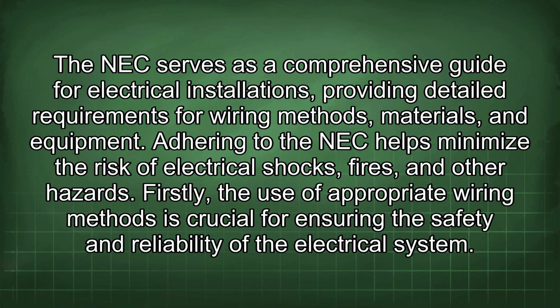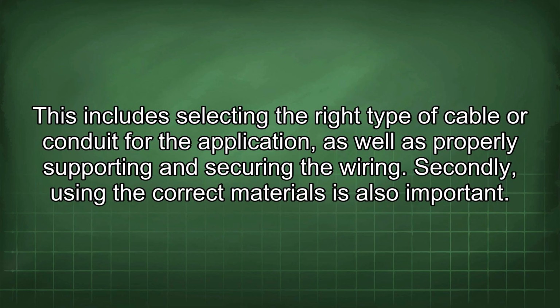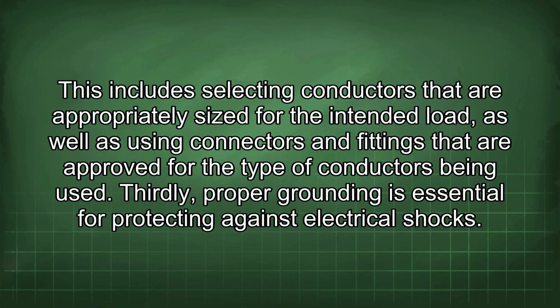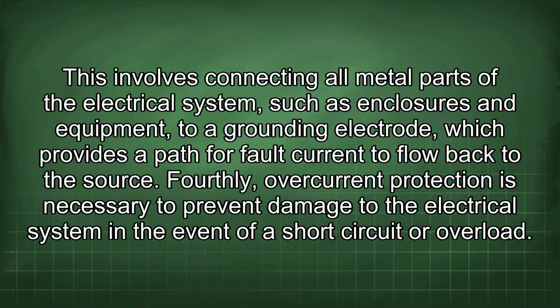Firstly, the use of appropriate wiring methods is crucial for ensuring the safety and reliability of the electrical system. This includes selecting the right type of cable or conduit for the application, as well as properly supporting and securing the wiring. Secondly, using the correct materials is also important. This includes selecting conductors that are appropriately sized for the intended load, as well as using connectors and fittings that are approved for the type of conductors being used. Thirdly, proper grounding is essential for protecting against electrical shocks. This involves connecting all metal parts of the electrical system, such as enclosures and equipment, to a grounding electrode, which provides a path for fault current to flow back to the source.